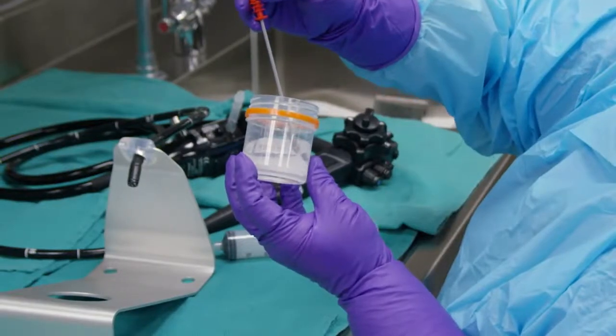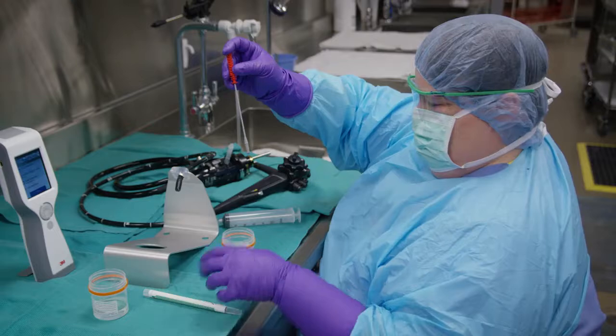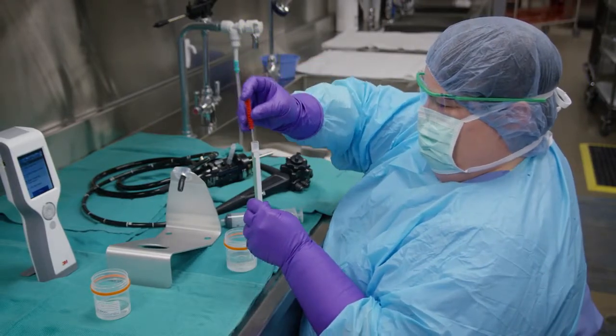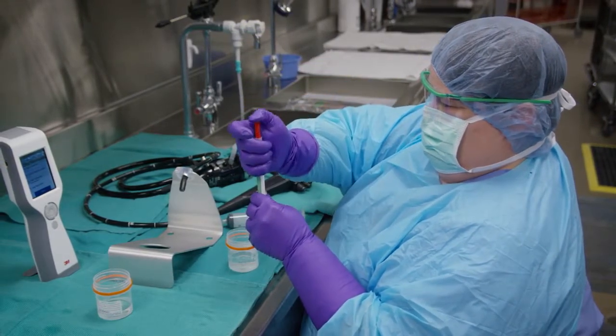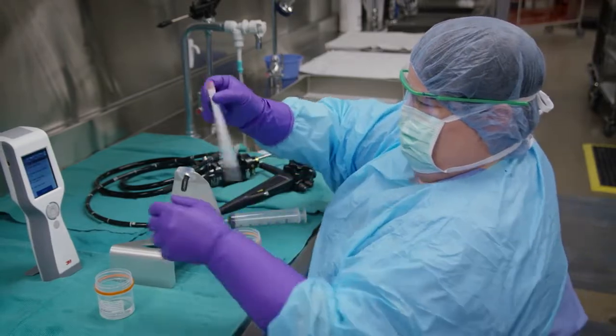Now, there are a number of different kinds of tests that can be used for cleaning verification, and these can pick up very small residues of protein, hemoglobin, or adenosine triphosphate, which is called ATP in the field. ATP is just a substance that's secreted by any living cells, and so it's a marker that would tell you if there still is soil there. When you do that cleaning verification test, if it shows there's still soil, you could re-clean the endoscope prior to subjecting it to the high-level disinfection or sterilization process.